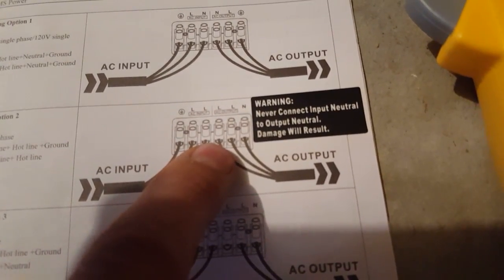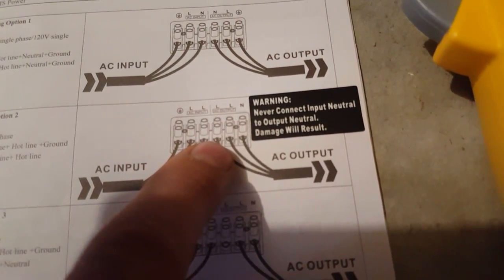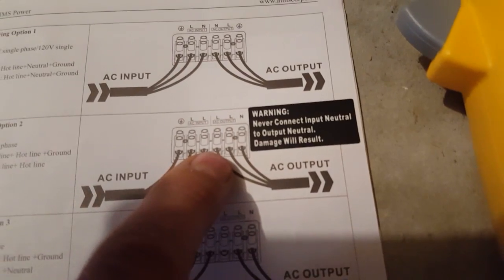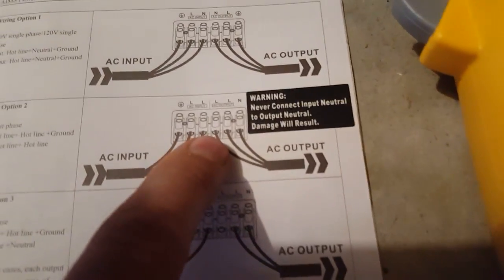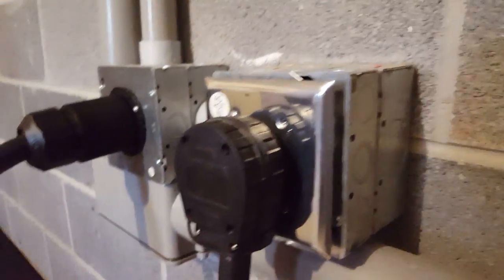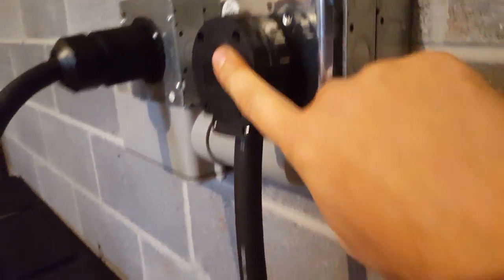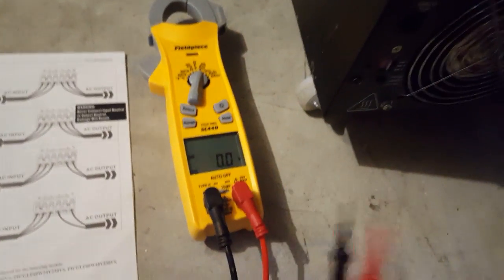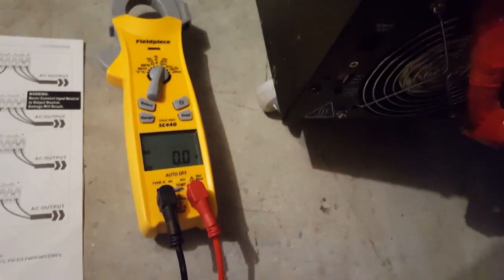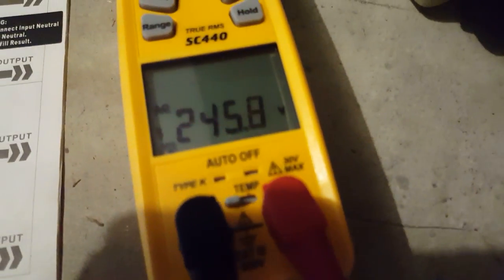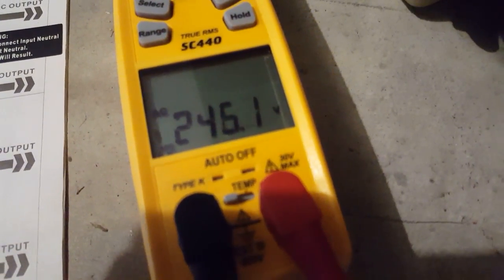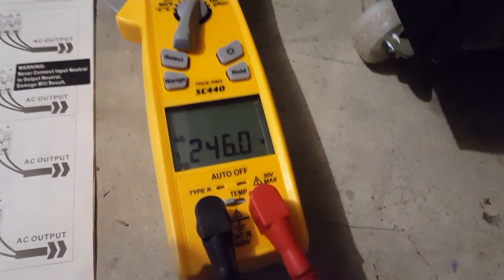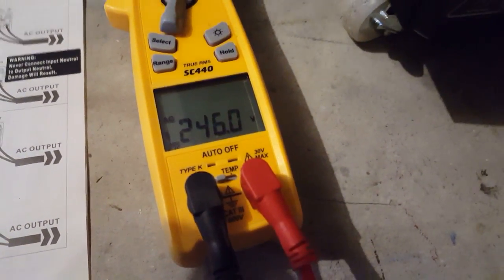Let's, we've got our inverter plugged in, okay. Right now we've got our two test leads. We're gonna take leg one, leg two. This is input power, not output power, this is input power. Okay, there's 246.1 or so, and that's the high voltage from the main panel going in.